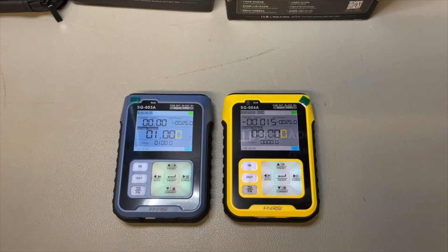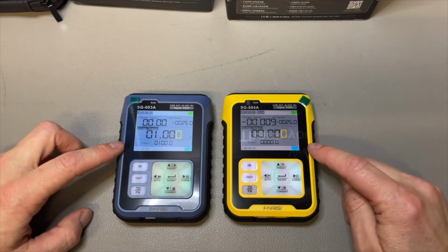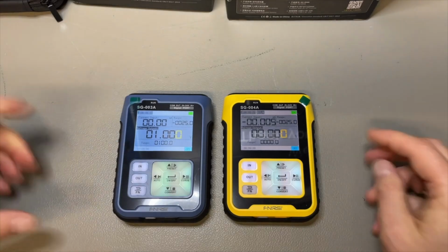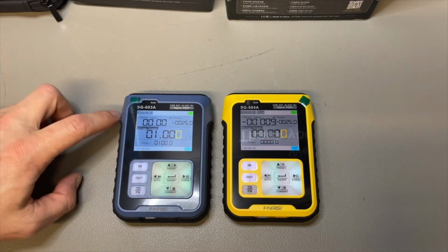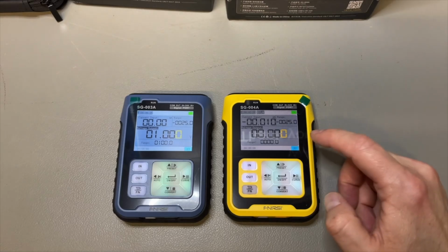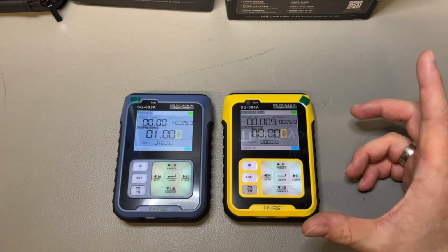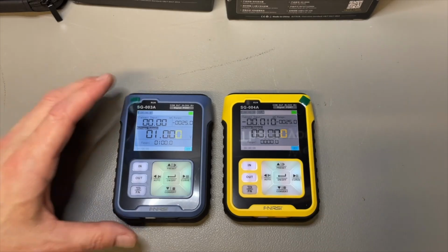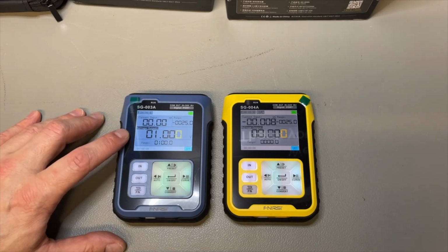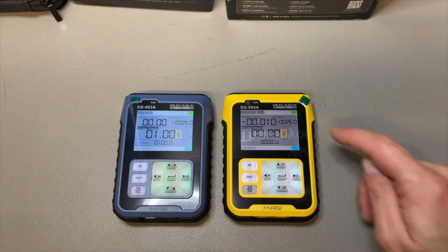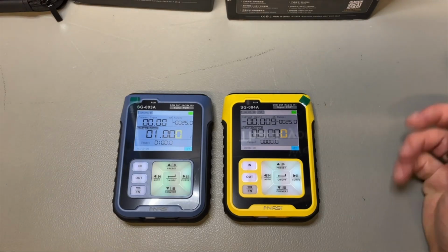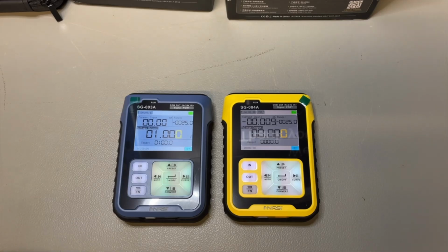So if you're planning to use it for multimeter calibration, maybe you can recalibrate it against a 6.5-digit multimeter, but still, this one is 0.1% and this one is 0.02%. So using it as a calibrator, maybe for a 3.5 digit meter, this one maybe 3200 counts, and this one maybe 6000 counts - it's not actually made for it, but you can do at least your basic tests.